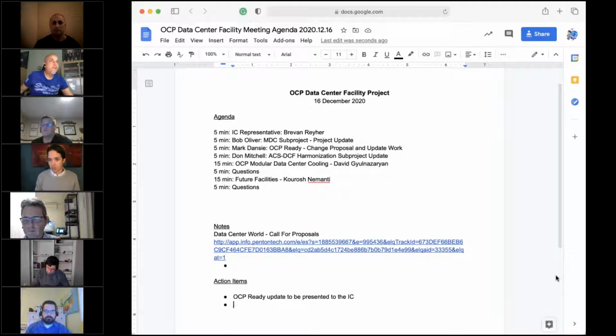People have always assumed liquids would likely be below dew point, and designed their liquid distribution accordingly with insulation, condensate trays, and things of that nature. We're getting to a point where many data centers don't have to. So the ACF guidance might be something like: if you're planning on putting in liquid cooling, considerations need to be made whether you're going to maintain either the data center humidity or the liquid temperature at levels that avoid dew point, because that affects the design guidance being provided.